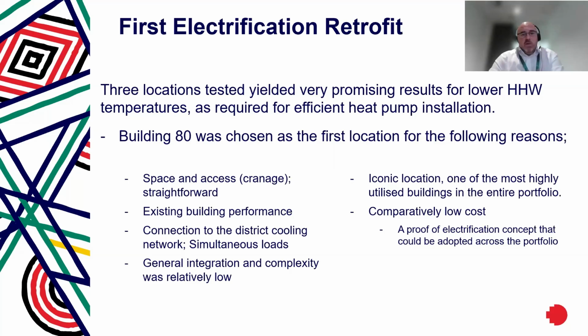So once we'd done the testing, we did some rationalization of the results, and determined where we were going to go first. We chose RMIT Building 80, and we did that for space, access, complexity. We knew the existing building performance was appropriate, so double glazing, insulative performance, etc., and therefore the loads were likely to be rationalised to the best extent. It was connected to our district cooling network underneath Swanston Street, so we were able to get a fairly large cooling load, and we were able to do some simultaneous heating and cooling with a four pipe.